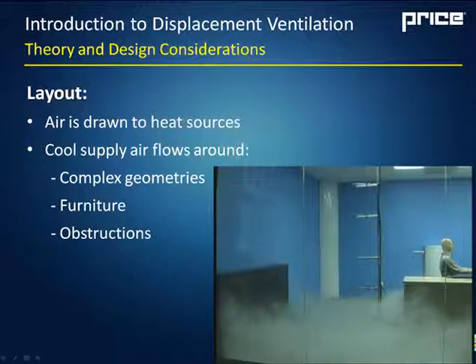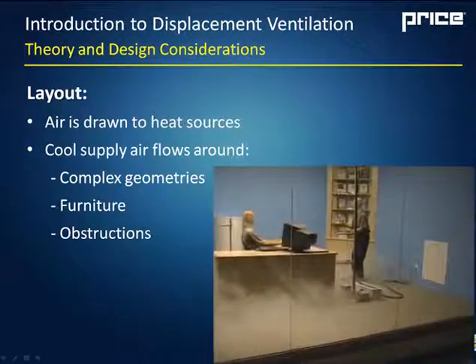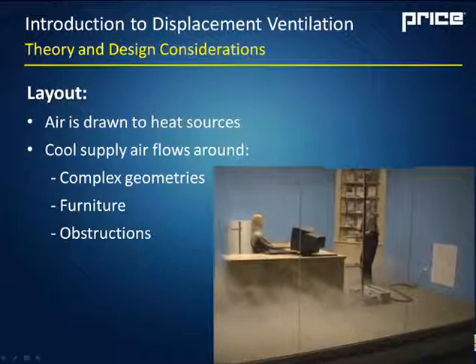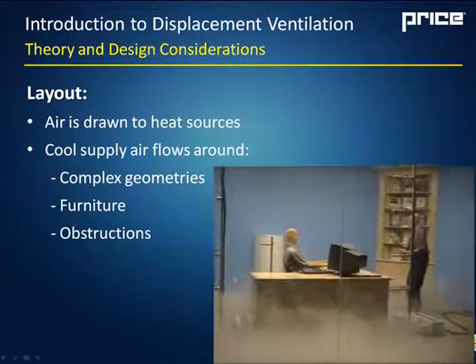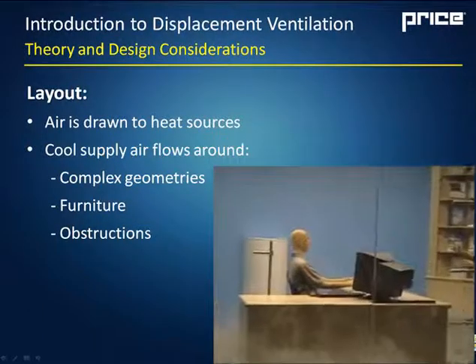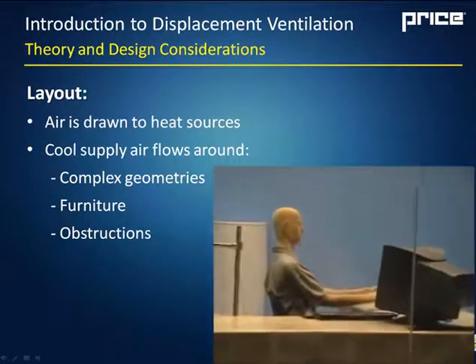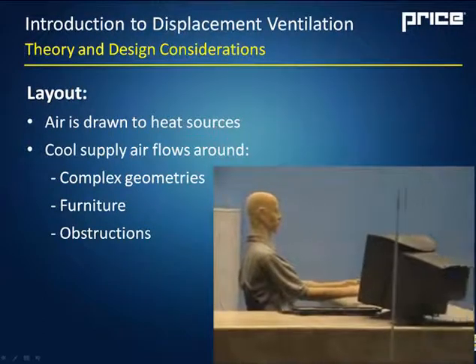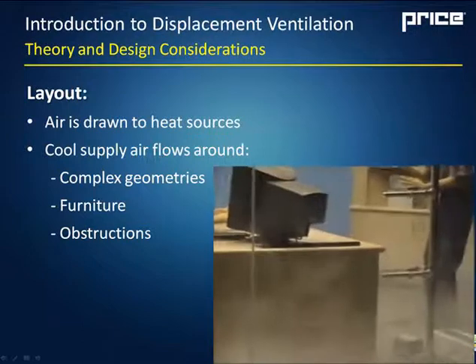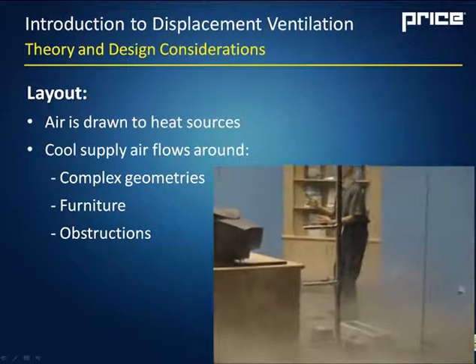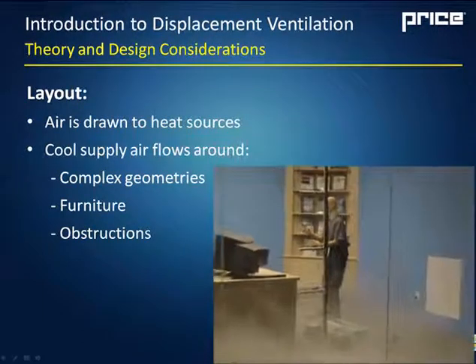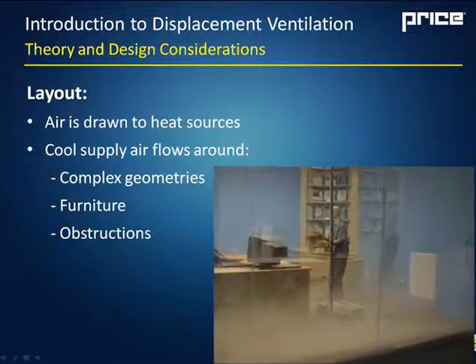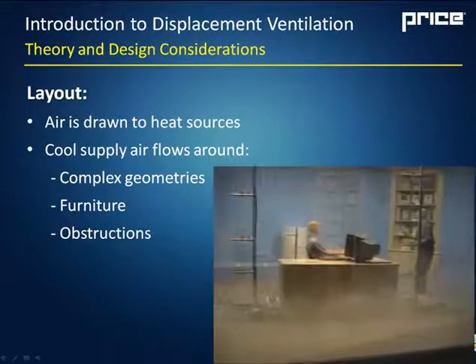Now, what you can see from the video here is the air has been introduced from that corner diffuser. It's spilling across the floor. The mannequins are heated, so you'll see it start to develop thermal plumes around the mannequins. And it's spreading all the way across the floor into the far corner of this room, just from that corner diffuser. So even it's going around the desk, around all the objects in the room, and you can see it start to pull the smoke up the warm mannequin. So the layout is far more simple with the displacement ventilation system.